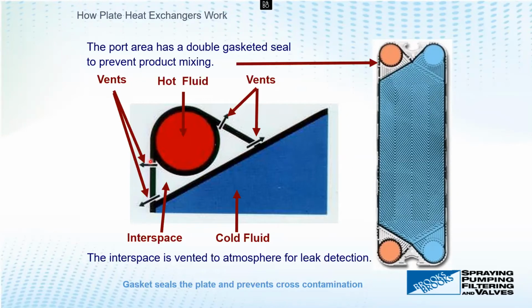Should there ever be a failure in this gasket for whatever reason, there are vents. Those little tiny holes I showed you in the previous slide are actually there on purpose. They're little vents allowing the hot fluid, in this case, to vent to atmosphere so it doesn't intermix through the flow gasket.